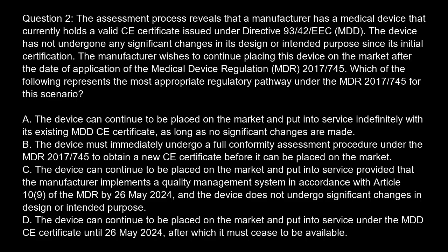Option C. The device can continue to be placed on the market and put into service provided that the manufacturer implements a quality management system in accordance with Article 10(9) of the MDR by 26 May 2024, and the device does not undergo significant changes in design or intended purpose. Option D. The device can continue to be placed on the market and put into service under the MDD CE certificate until 26 May 2024, after which it must cease to be available.